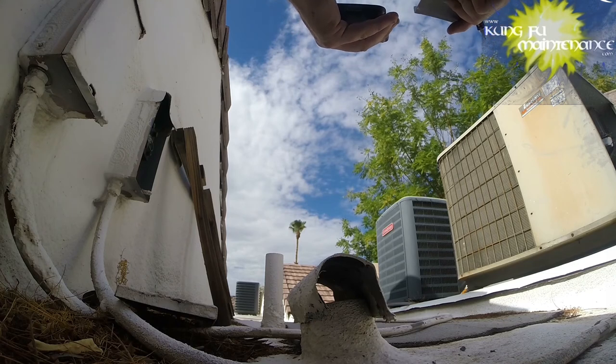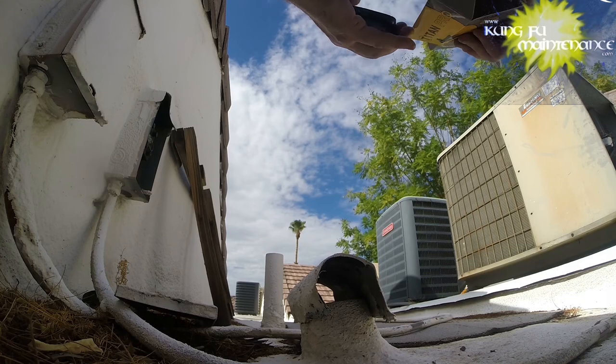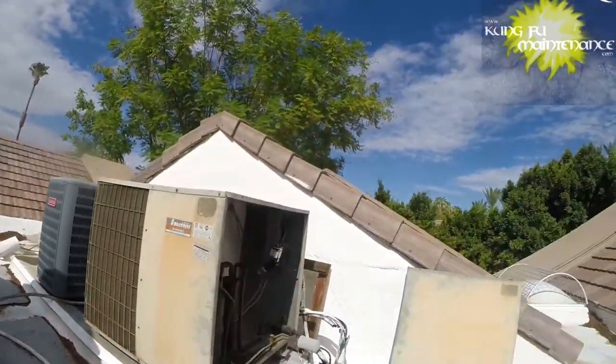Okay. We're looking at this as I made the video. I took the 2650 times 5 and then divided it by what is the rated voltage, which is 370. And I got now on the capacitor 35.8 microfarad.